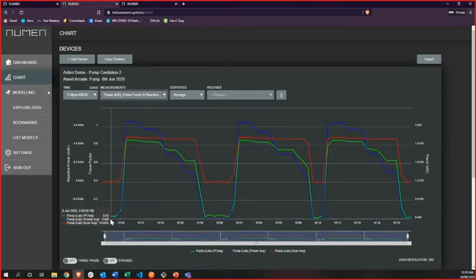Here you can see in time series, the blue line is the power consumption of the pump as it goes down, the green line is the power factor, and the red line is the reactive power. You can see how the reactive power stays essentially constant, while the real power goes down as the pump starts cavitating, which then affects the power factor.